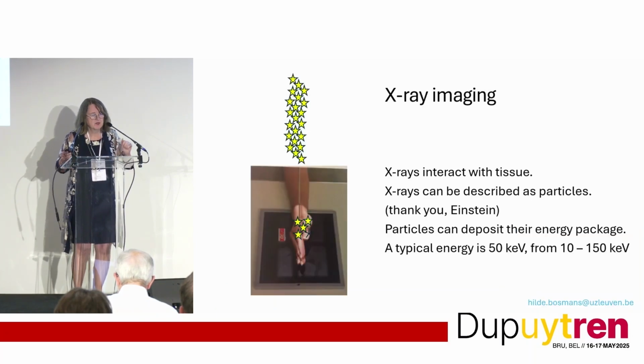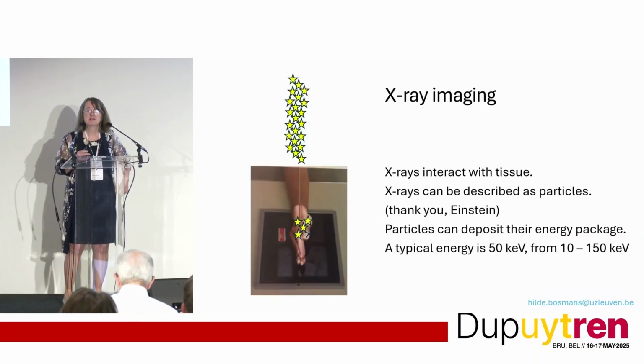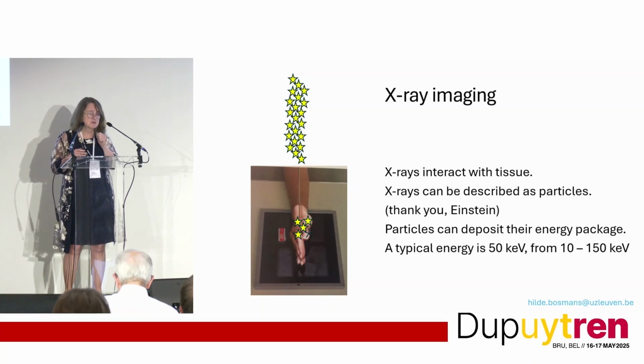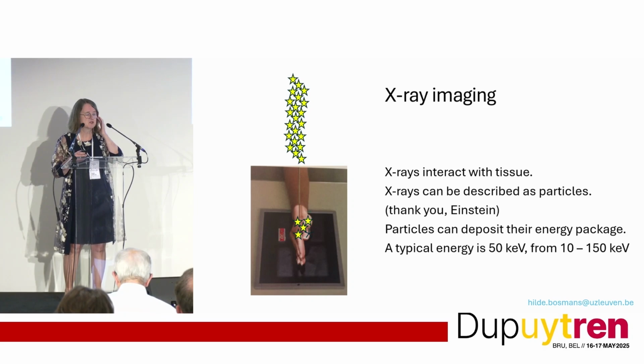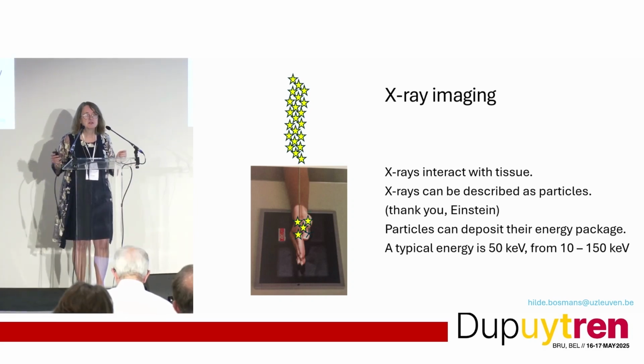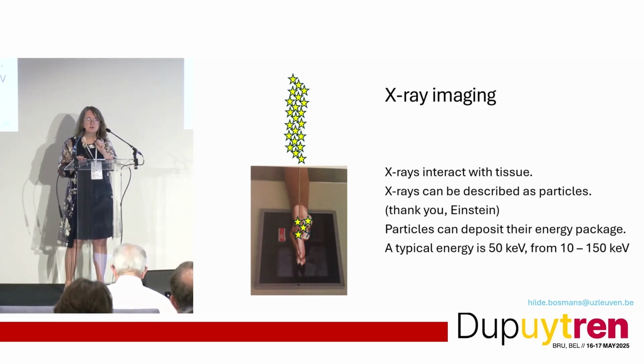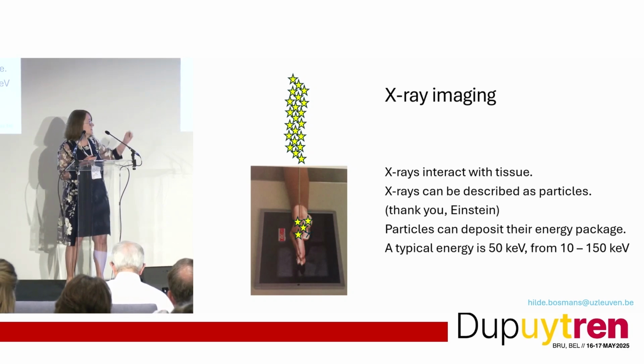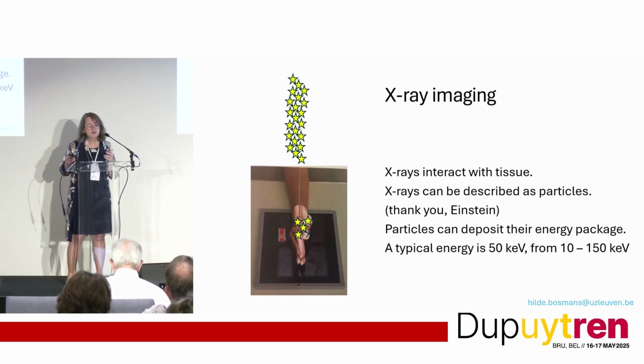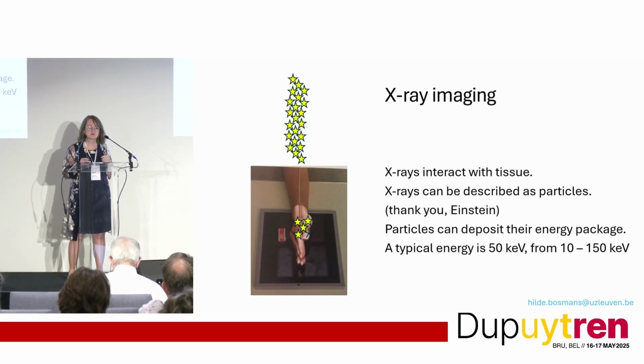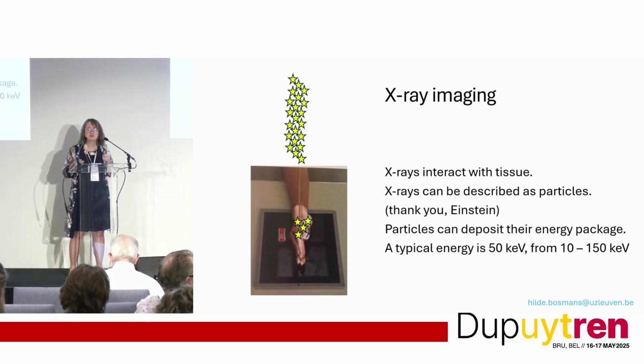Okay, so X-rays are going to interact in the hand. Some particles will completely disappear from the beam, some will in part disappear, and some go through the hand. If everything were absorbed in the hand, there would not be a picture. Some go through the hand to make the ultimate picture. The energy packages that are absorbed from the beam are typically in the order of 10 to 150 kilo electron volt. That depends on the kV that we set.